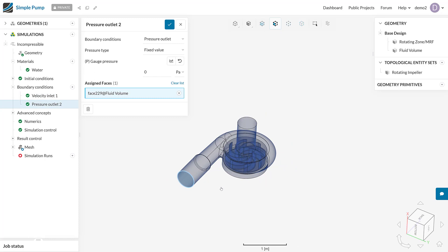What is very typical of these types of cases is that we want to understand what the efficiency is. This is an incredibly good case to demonstrate some of the result controls available in SimScale that allow you to output things like pressure drop to find hydraulic power. Alternatively, we might want to find the shaft power, or the power that we are putting in at the shaft to make this flow happen. That can be calculated using the torque applied to the pump to maintain that flow. We can do both of those things by using some additional result controls.